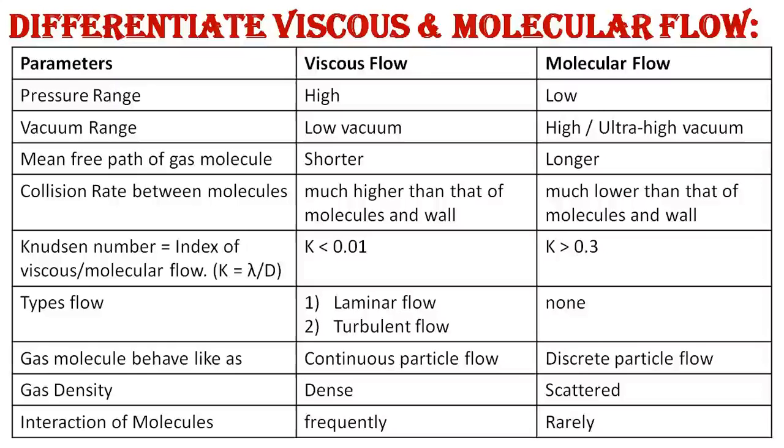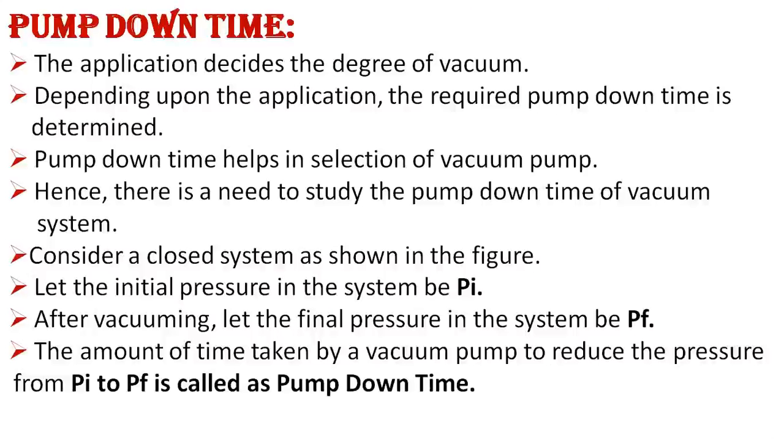Now the next concept is the pump down time. The application decides the degree of vacuum. Depending upon the application, the required pump down time is determined. Pump down time helps in the selection of the vacuum pump.